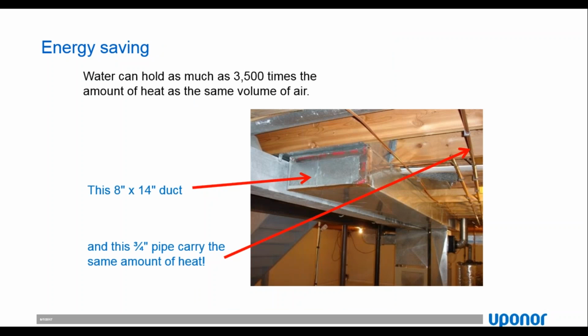Besides that, one of the other benefits of radiant heat is energy savings, because water can hold as much as 3,500 times the amount of heat as the same volume of air. As you can see in this drawing, an 8x14 duct carries exactly the same amount of energy as a 3/4 inch pipe filled with water—so you can see the space-saving capability.